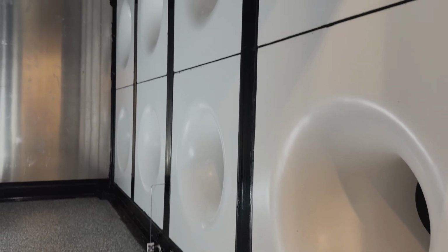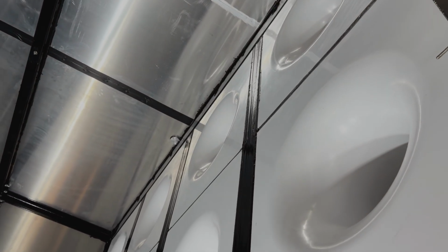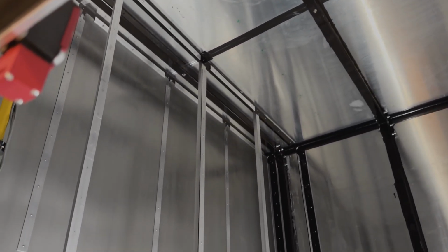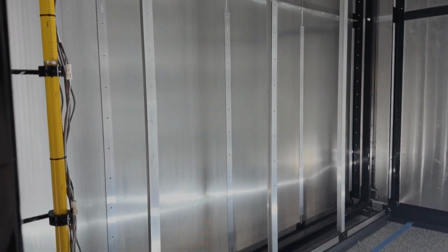Why is that important? It's very important. It's something I neglected to mention earlier. This tunnel was purpose-built to meet the AMCA 270 standard. AMCA 270 is a fan array standard for building an instrument to get reliable data for fan arrays. But that profile has to be exactly to the thousandths of an inch correct, so that when we're measuring pressure difference across that wall, we know that we're measuring against a specified geometry.